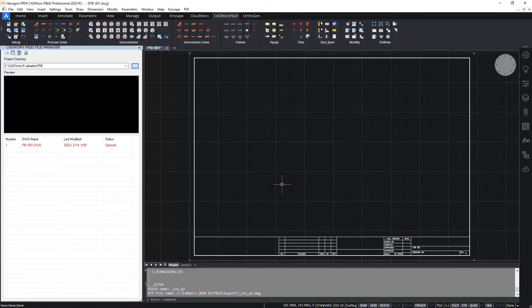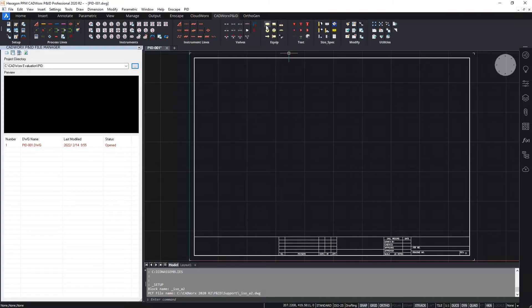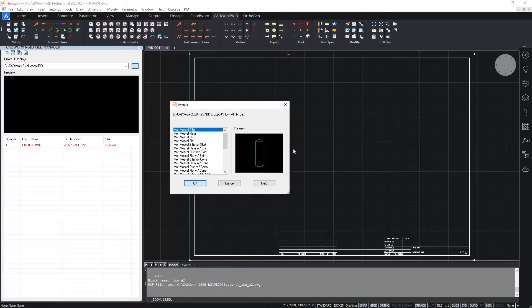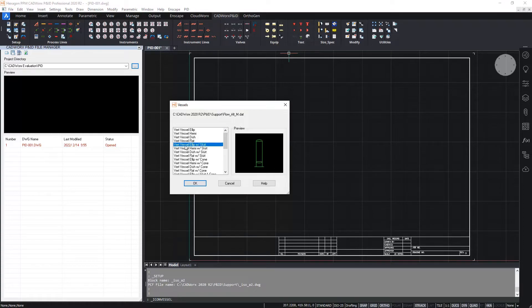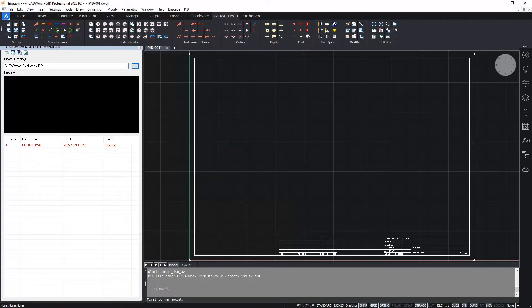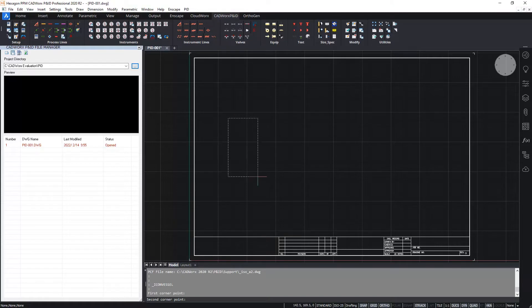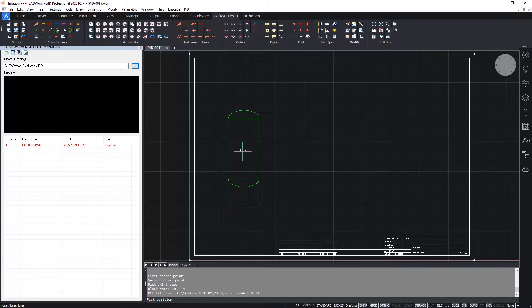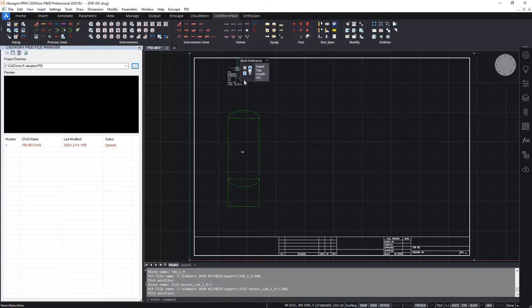Now we've added the border, let's insert some symbols. I'll start with the major equipment. So I'm going to start by placing a vessel. All of the symbols available are on the ribbon here, so the vessels icon provides me the available vessels in the current symbols library. I'm going to choose a vertical vessel with elliptical ends with a skirt. And then I just position the vessel. The drawing routine for the vessel is straightforward. I place the rectangle, the heads are placed automatically, and then I now attach the skirt. The vessel symbol also has a tag item and a label item associated with it. So I will position those as appropriate.